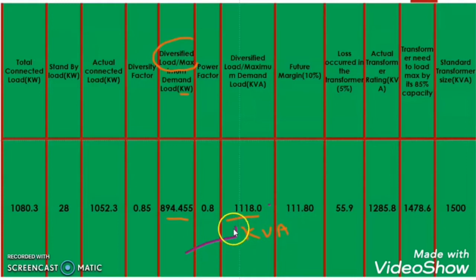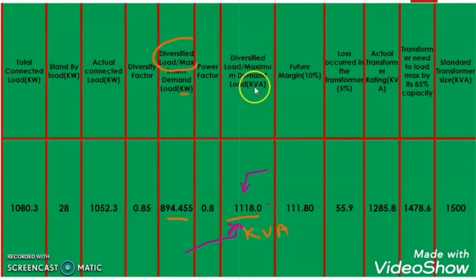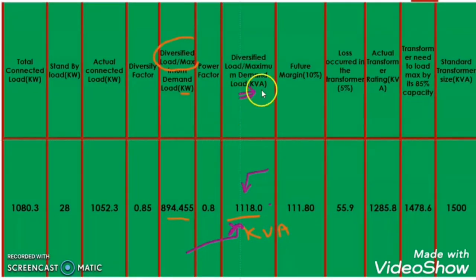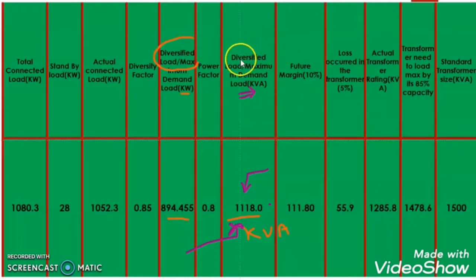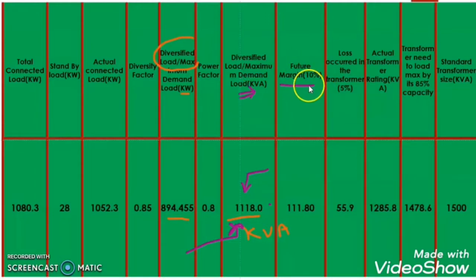If we select the same size of transformer as the diversified load, we cannot add any future load, because the kVA rating of the transformer would be exactly equal to the total load. As I mentioned in my previous video, a transformer is a one-time investment — we cannot change it frequently. So we always need to consider a future margin. Generally, 10% to 15% is taken as a future margin. I took the future margin as 10%, which is 111.8 kVA.